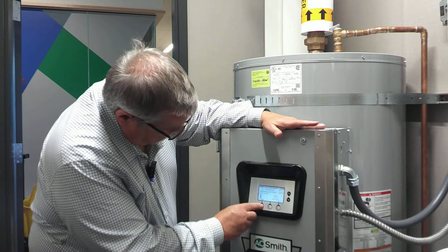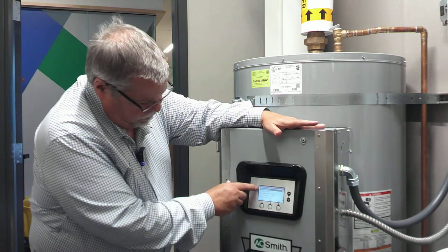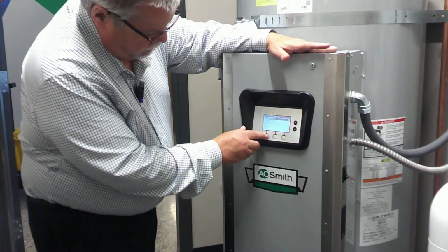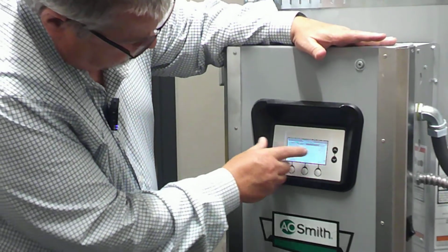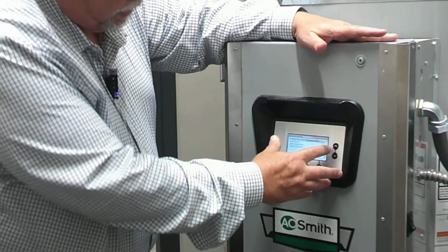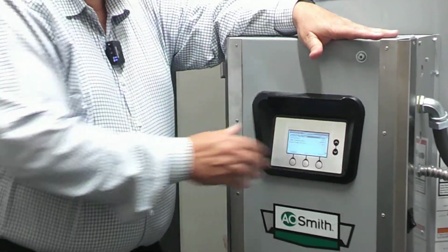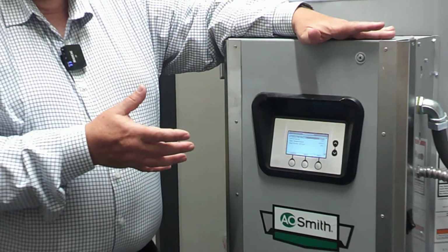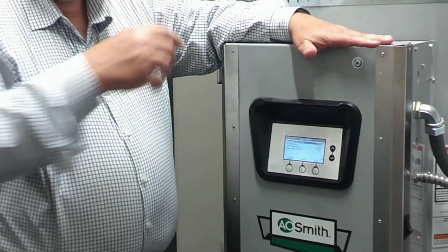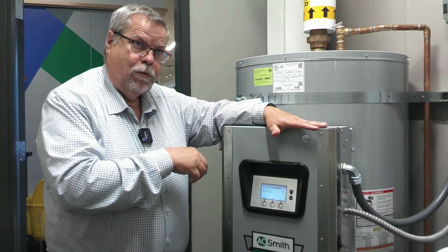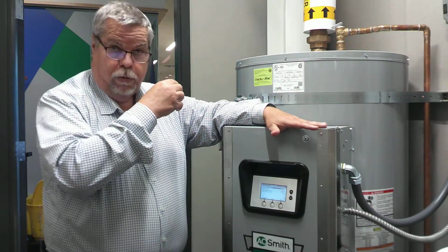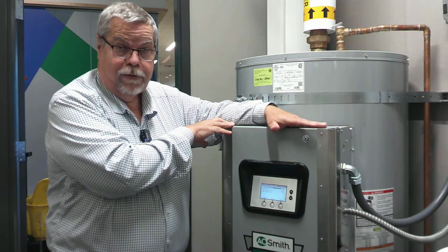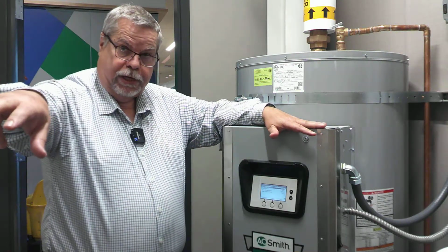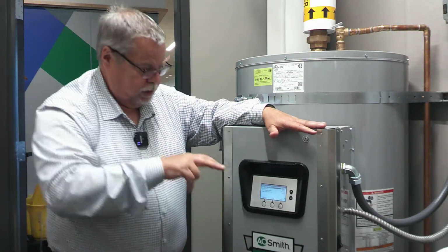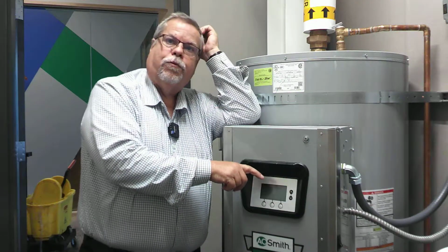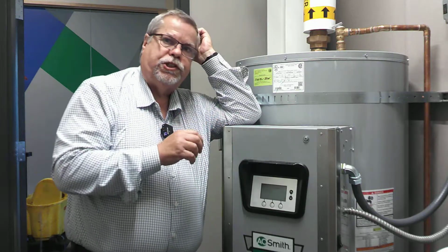You push the button, the light goes on, the light can be set on, and you have to set temperature. You'd go to the temperature, you would select it. The differential on this is set at 3 degrees. It's set to put out 120 degree water. 120 degree water is considered safe. So this is protected by a mixing valve, but if you were going above 120 degree water, and say this had 145 degree water, and now you have students that could get burned, someone will have to adjust that mixing valve in concert with this heater. It's got a 3 degree differential. That's for precision and control.